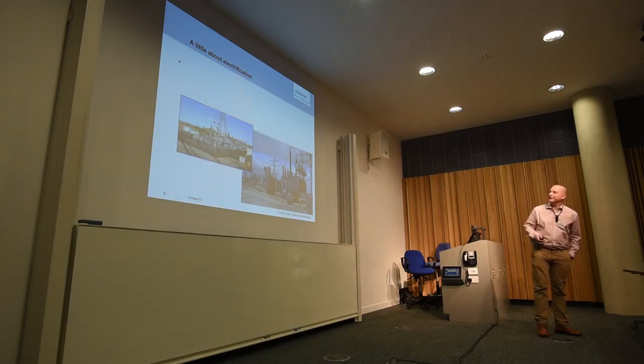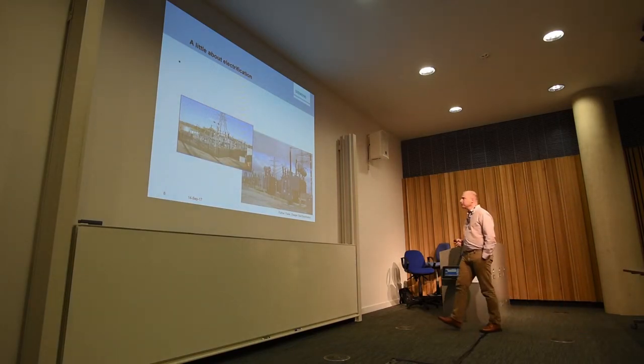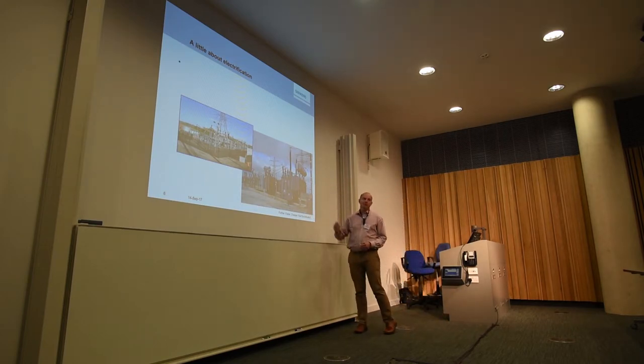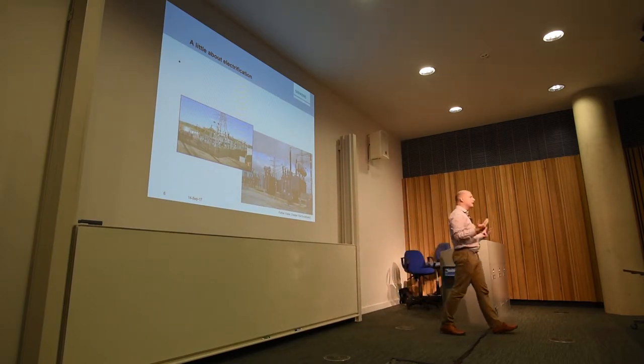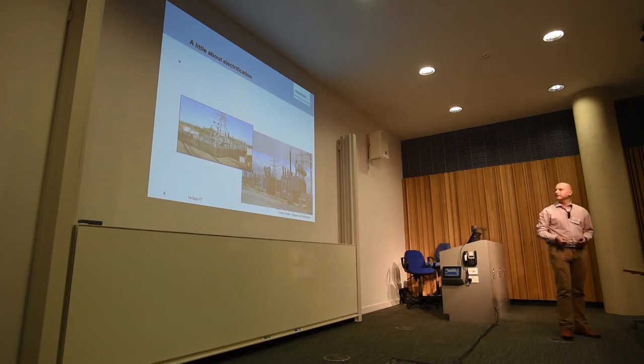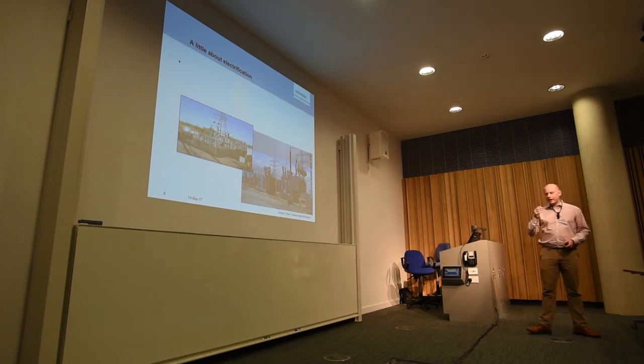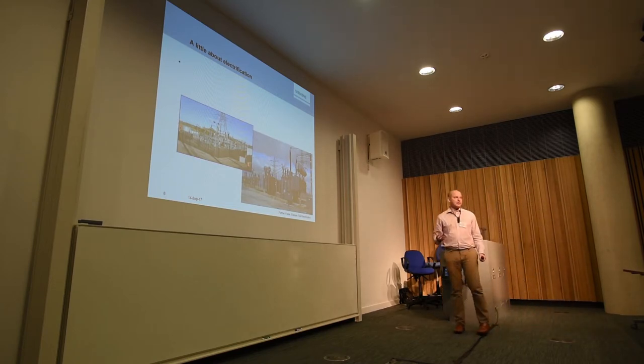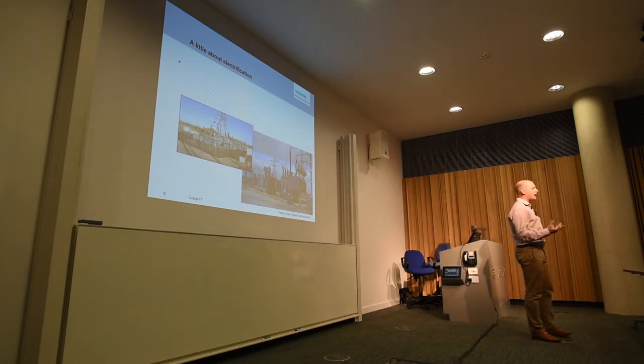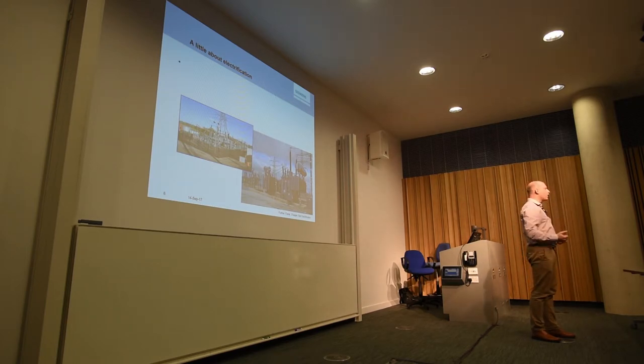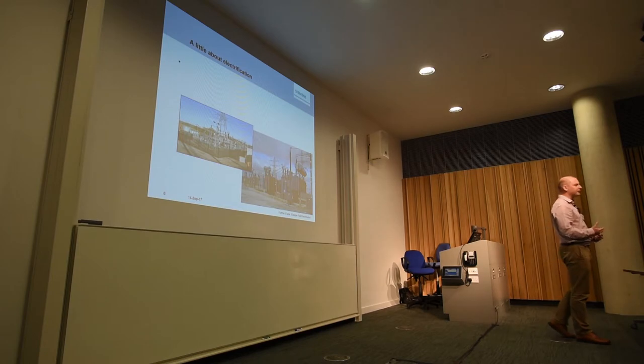So, AC electrification. This is typical. A supply taken from the National Grid or Distribution Network Operator every 30 to 50 kilometres typically. The eagle-eyed amongst you will notice there's only two droppers coming down from the three phases of the National Grid. That's one of the constraints we have with rail electrification. Because you've physically got to put a current collector in contact with a wire at very high speed, it's not feasible to get three-phase power to the train. So we are a single-phase network, whether it's DC or it's AC, we have a phase conductor, and a neutral, which is typically the rails.